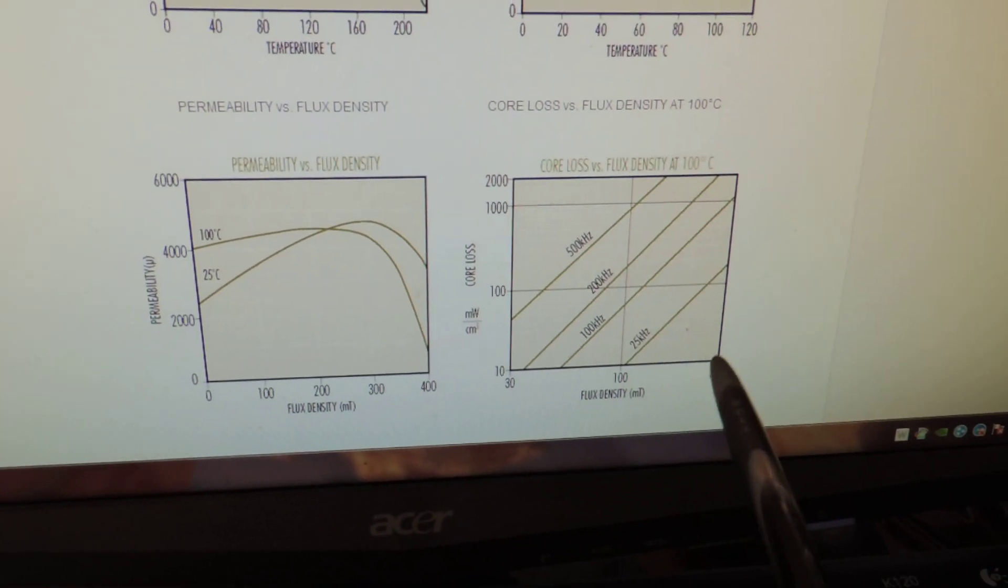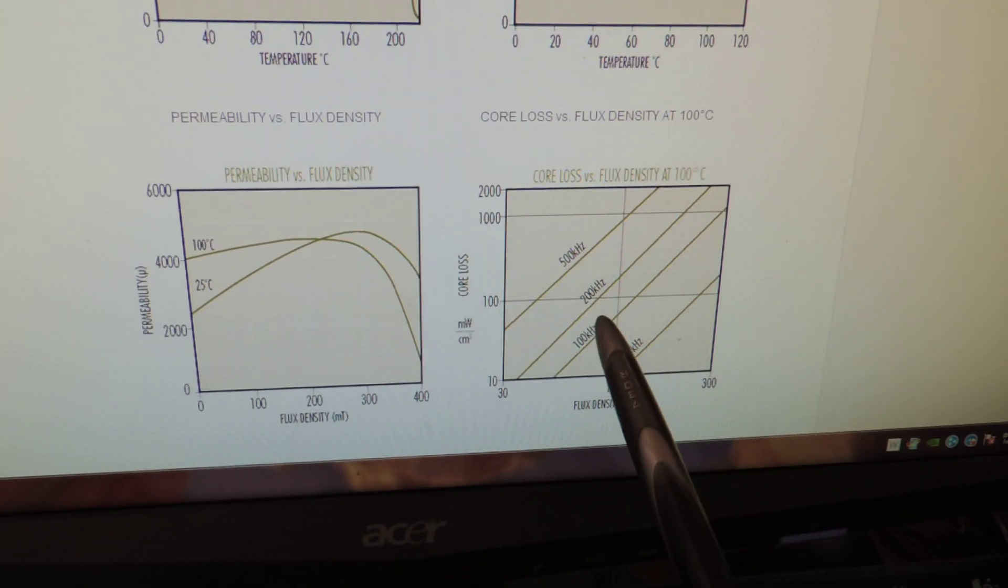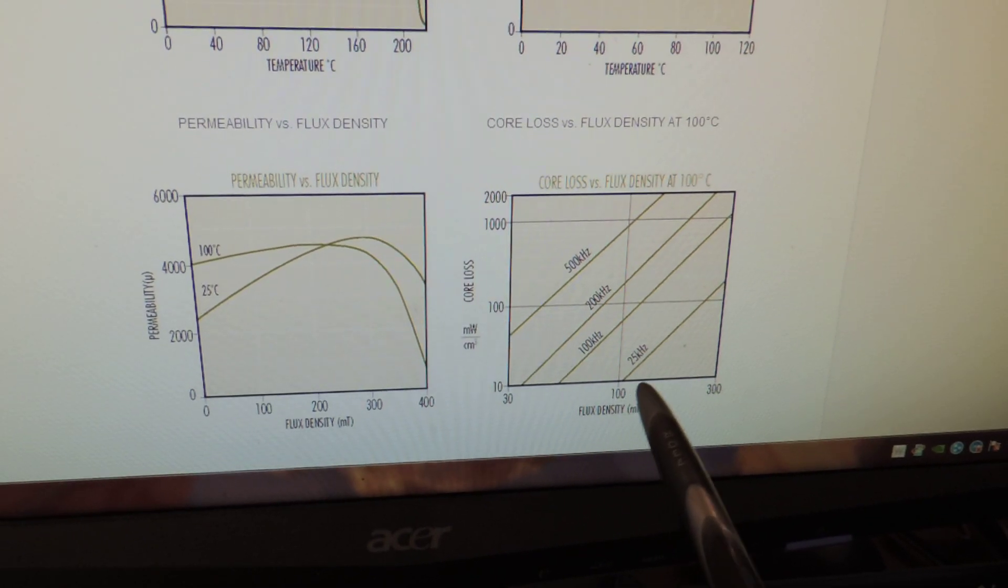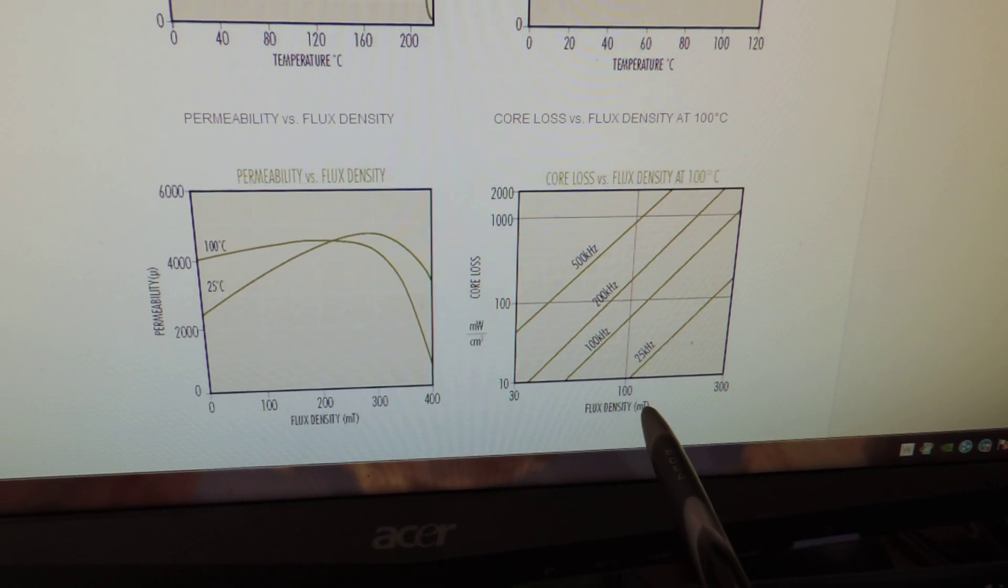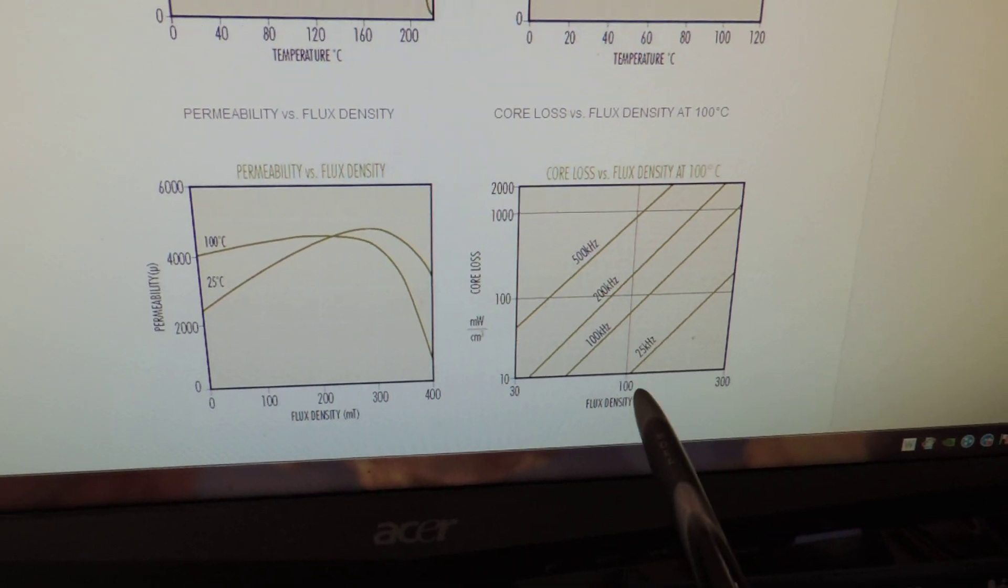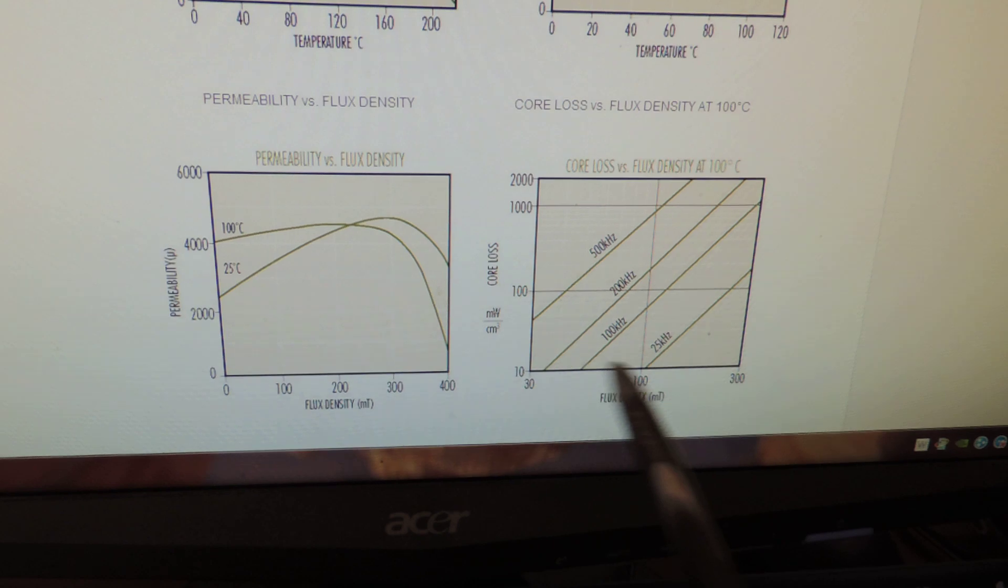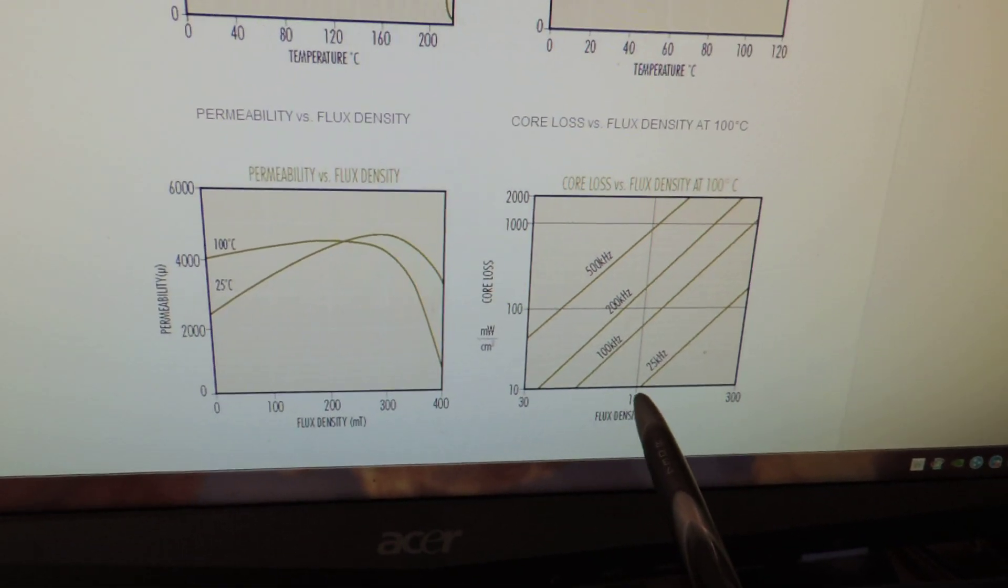A way to make your losses lower is either one, use a lower frequency, two, use a lower flux density. And for a lower flux density, that would either mean using a larger core, or more turns, or both. Those things right there can actually be used to make your core losses lower.